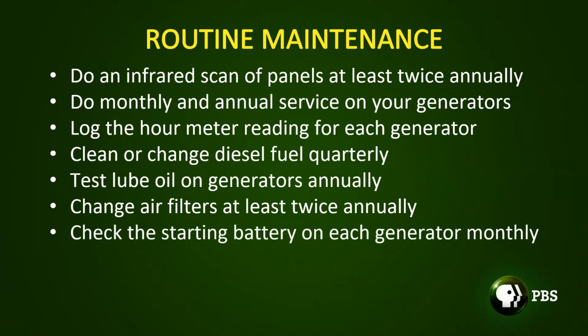Speaking of starting, the generators have a battery, just like your car or any other internal combustion device. Do a specific gravity check on the battery on each of your generators every month. And by the way, avoid the temptation to use a car battery for your starter battery, because car batteries do not take the type of charge and discharge cycle that emergency generators put on a battery.